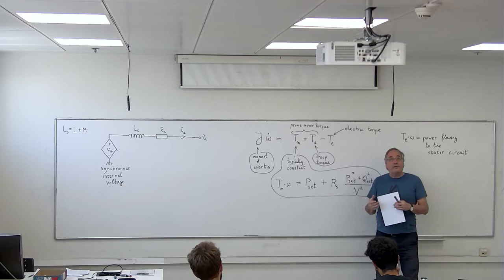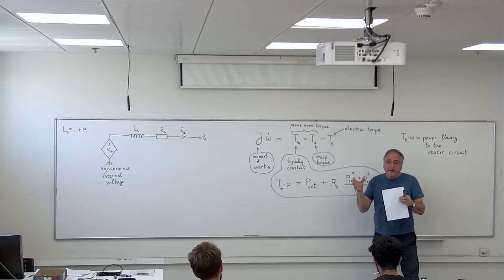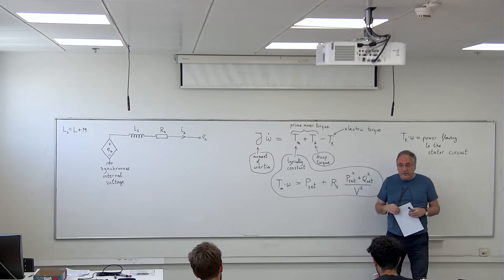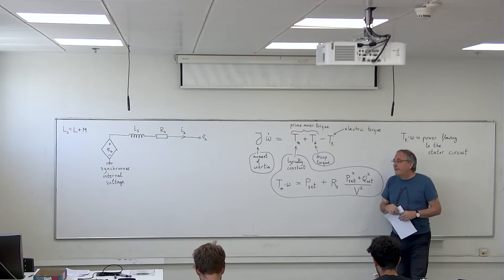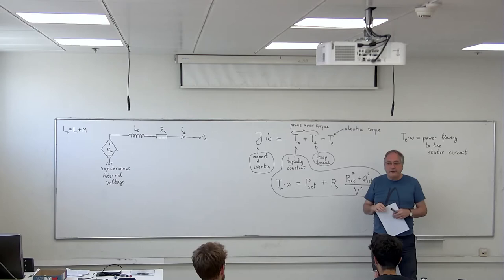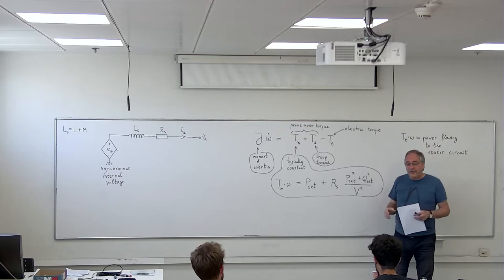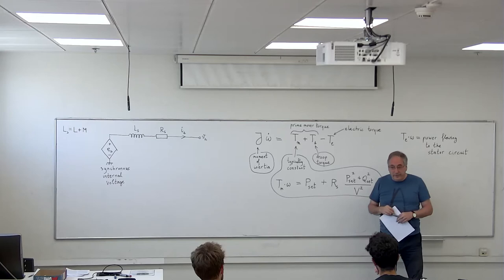frequency. Now, there is a similar situation at large generators. They can shake very violently if they are not at the correct frequency. So for this reason, the power grid is operated in a very narrow range in most of Europe and also here in Israel. This range is typically plus minus half a percent. So 1% would be half a hertz, so 0.5% would be plus minus 0.25 hertz around the nominal frequency of 50 hertz.